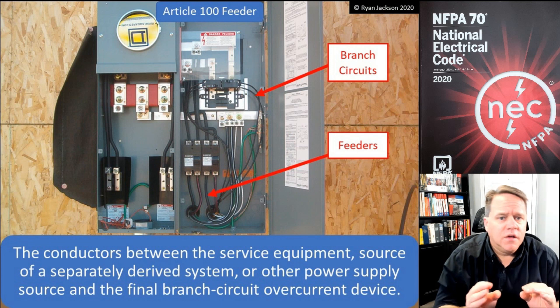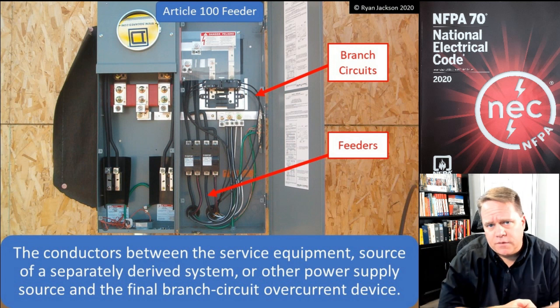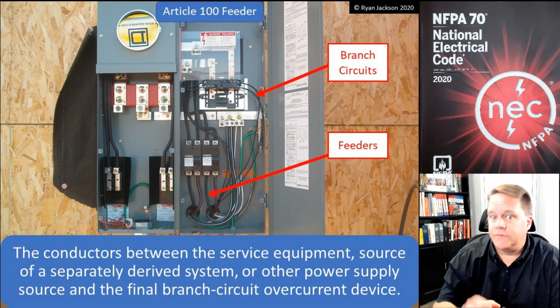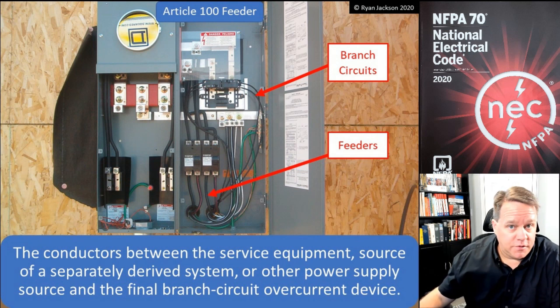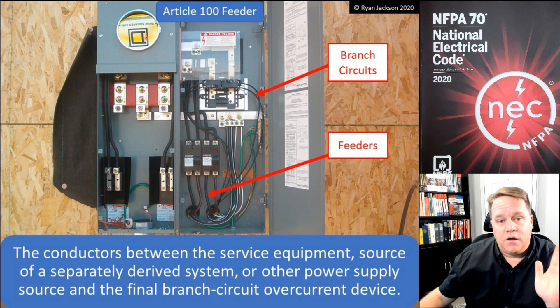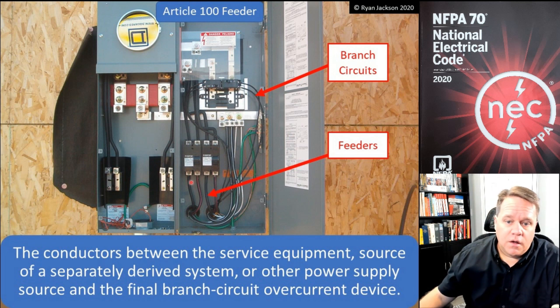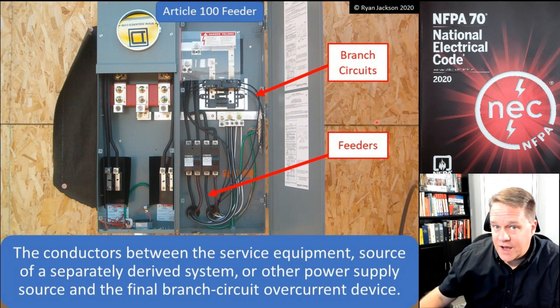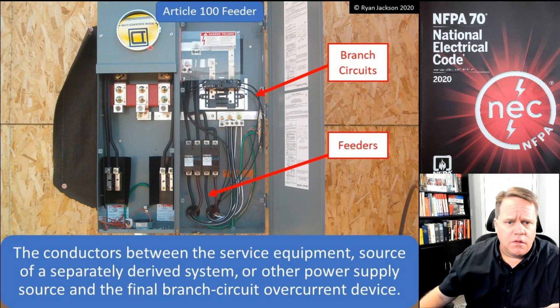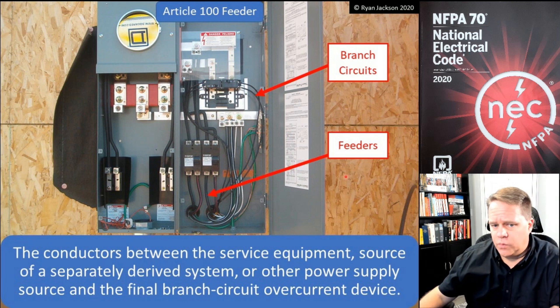It's really important that you know the difference between the two. A feeder circuit is defined as the conductors between the service equipment — which is the service disconnect, the first place you can shut off the utility. Looking at this equipment: on the left, the utility pulls in their conductors to the meter, and that's where the utility conductors end. Over here we have up to six service disconnects in this enclosure. The service ends at the service equipment, and that's where your feeder conductors would start.